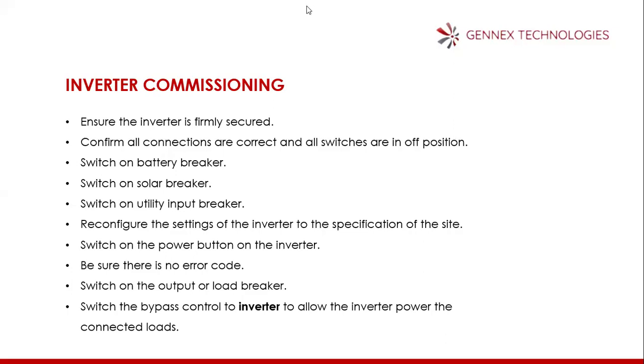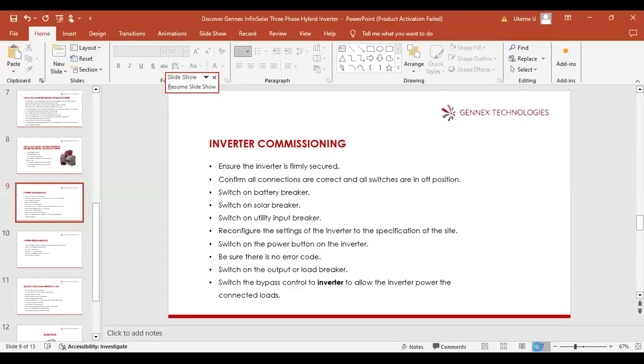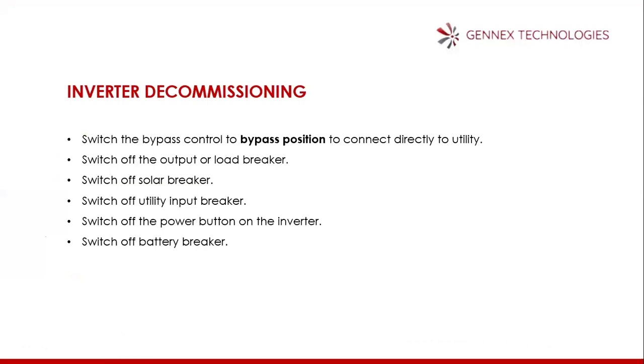Now, to inverter decommissioning, switch the bypass control to bypass position to connect the selected load to direct utility, either your generator or public supply. Switch off the output of the load breaker. Switch off solar breaker. Switch off utility input breaker.